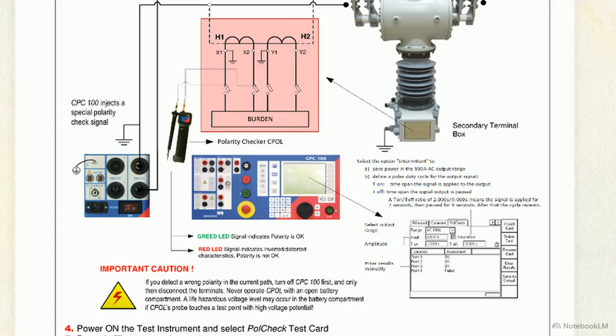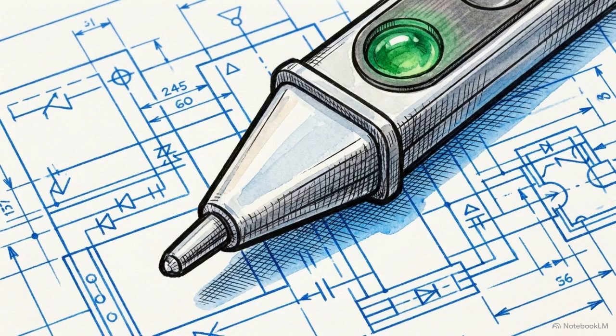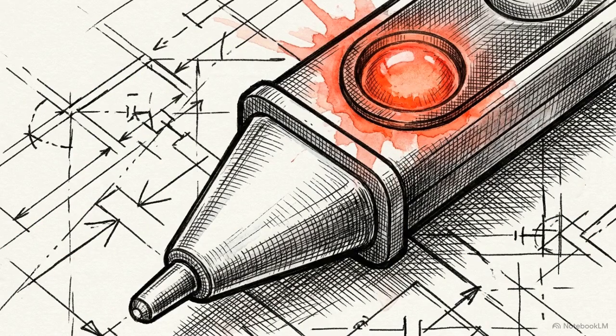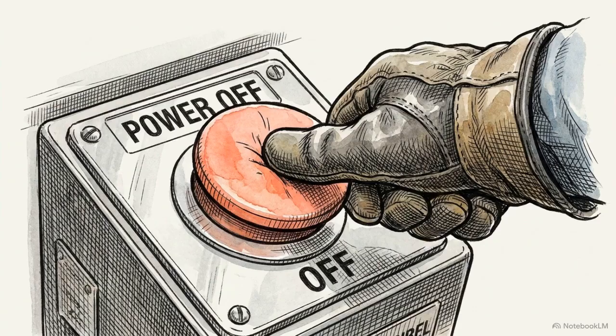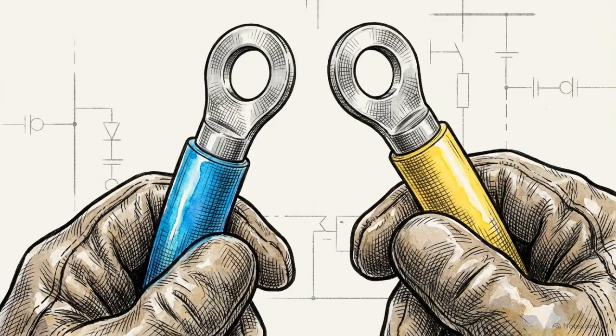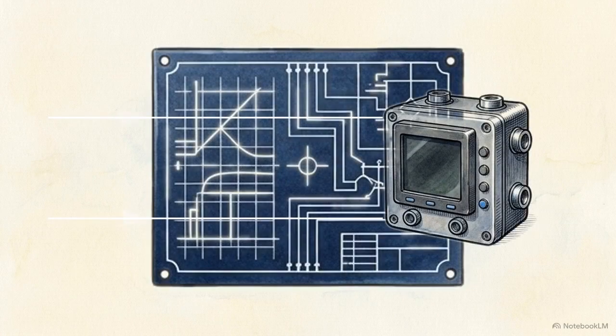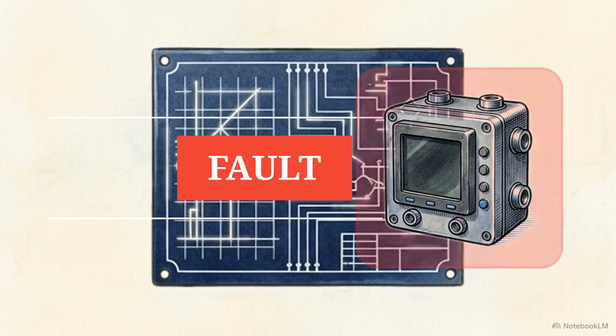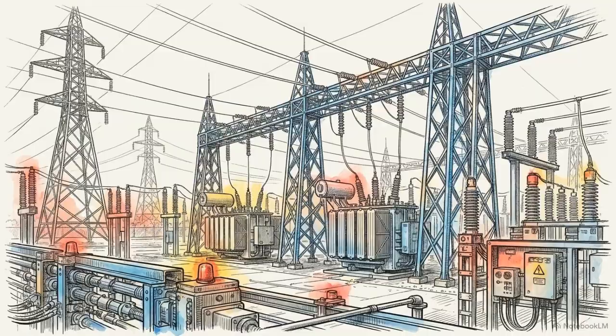If the checker flashes a green LED, the polarity matches the engineering design. A red LED indicates the signal path is inverted or heavily distorted. If a red LED is detected, protocol requires the operator to entirely power off the test set before attempting to disconnect or swap any field terminals. An inverted CT polarity will cause differential relays to miscalculate power flow, leading to immediate misoperation. Directional logic verification is the grid's final defense against false tripping.